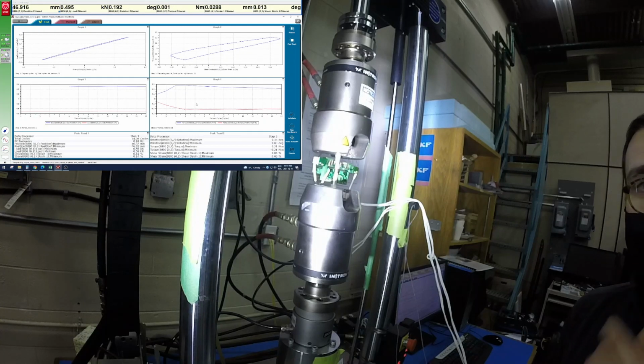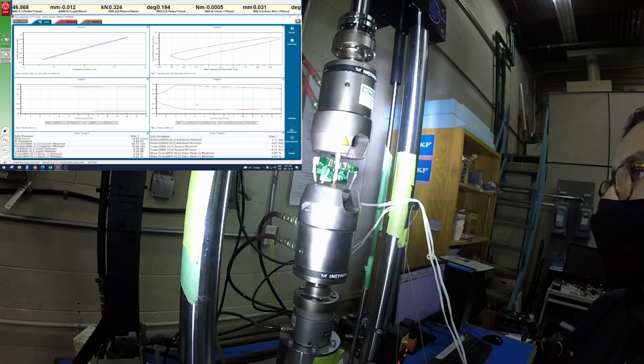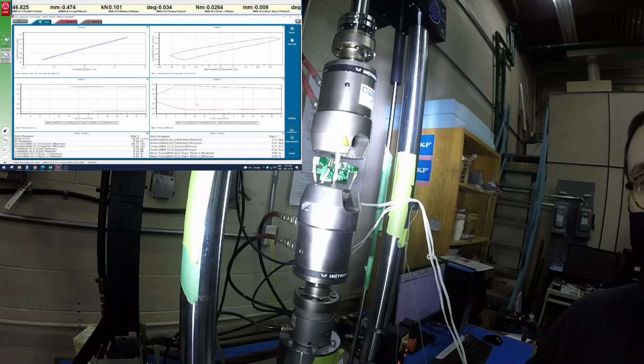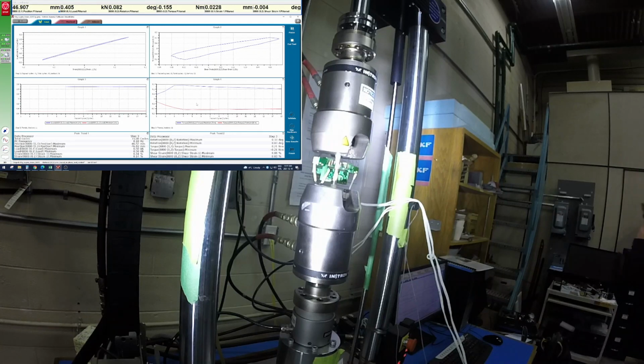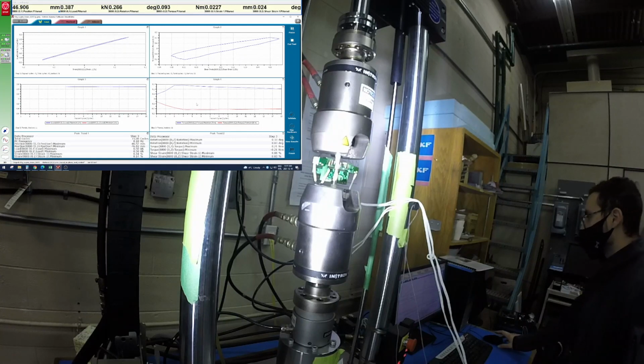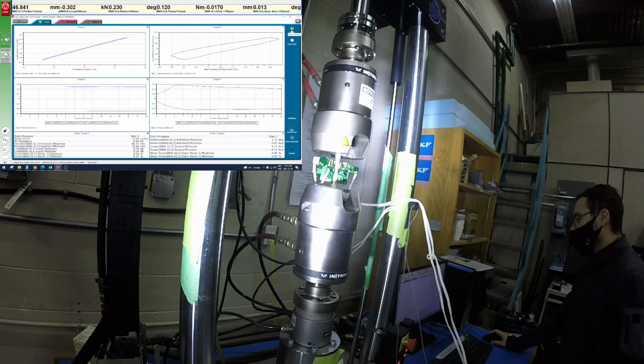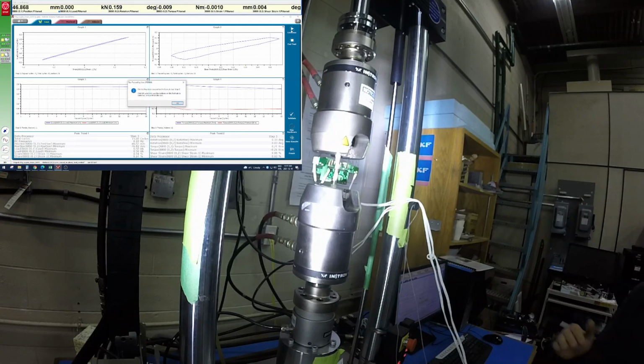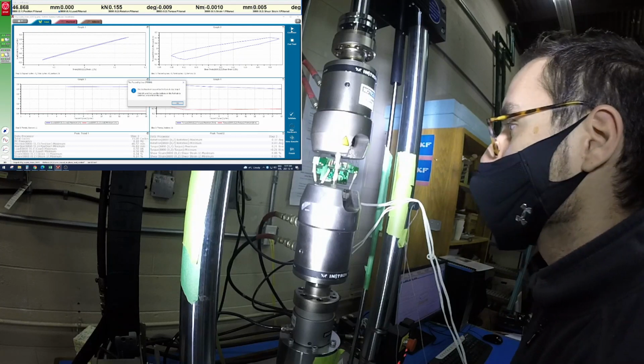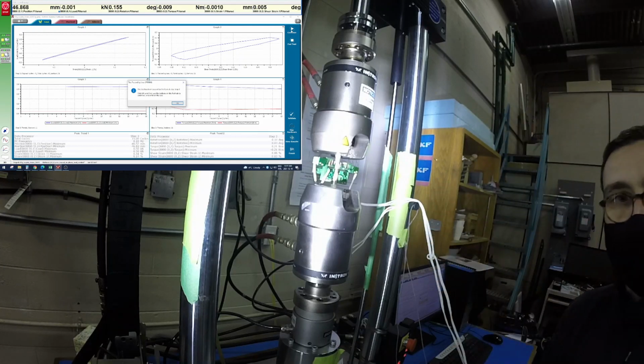And with that, I will sign off from this video SOP. I'll pause the test before we leave just to show you what you can do in the case that you need to pause it. If you click pause here, the test will stop exactly where it is, and you can see that it's going to default to the control modes that you've set up in the Wave Matrix software in the pause event. So this allows you, in case you need to adjust something or check something or go close to the machine, to pause the test.